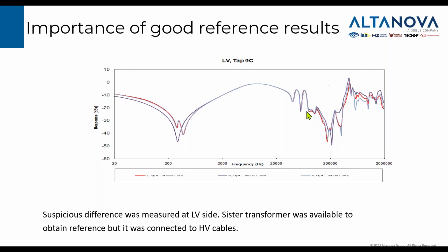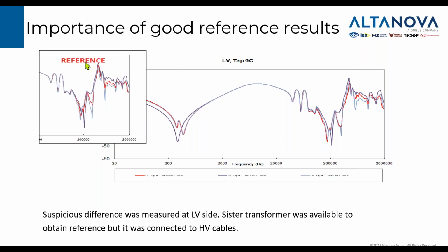There were still differences in the high frequency range, but this time as tested on the LV side with cable connected to the high voltage winding. So this was an additional influencing factor which I introduced to my test in order to be able to compare it with the transformer which I used for reference. And this is a reference which I obtained on the other transformer. So you can see, although not exactly the same, there were different cables connected to the high voltage side. But again, in this region, we had a similar response. So we understood this was a genuine feature of this design to have some differences in this region.